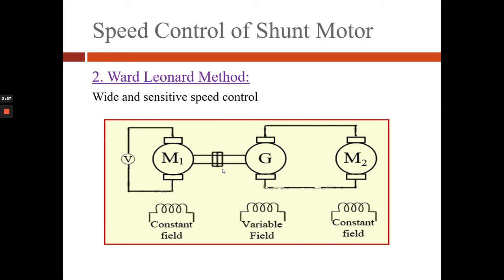Now we will see the Ward Leonard method. This is basically an armature voltage control of a DC motor. The variable armature voltage is obtained from a DC generator. M1 is a fixed-speed DC motor which is mechanically coupled to a DC generator. The output voltage of the DC generator is applied to the armature of DC motor M2, the speed of which is to be controlled. By varying the field current of the DC generator we can obtain a variable DC output voltage, which acts as the variable armature voltage for M2 and its speed can be controlled.